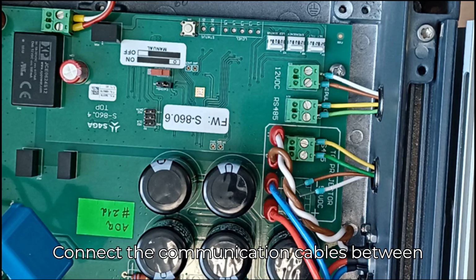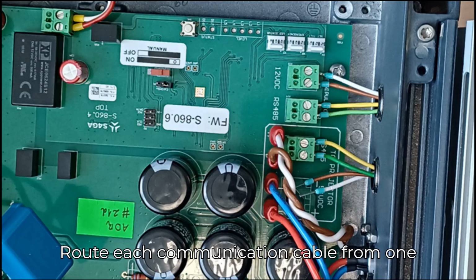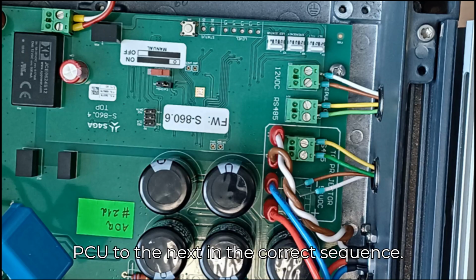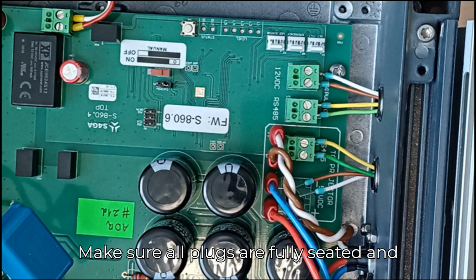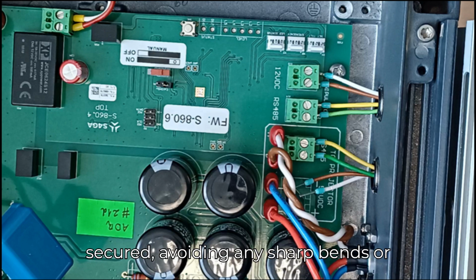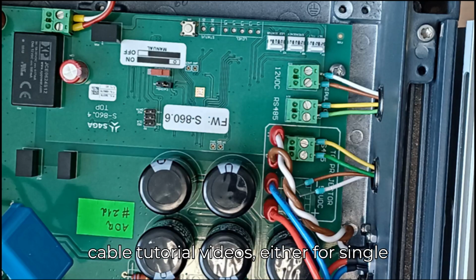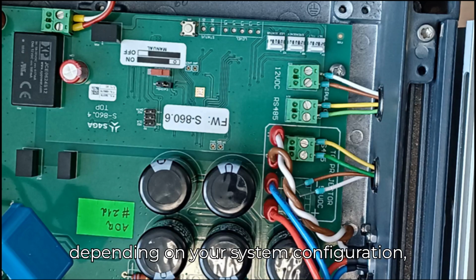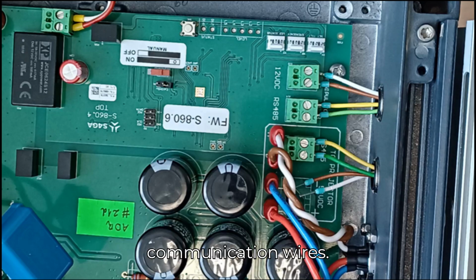Connect the communication cables between PCUs. Route each communication cable from one PCU to the next in the correct sequence. Make sure all plugs are fully seated and secured, avoiding any sharp bends or cable strain. Refer to the dedicated communication cable tutorial videos, either for single cable PCU or dual cable PCU, depending on your system configuration, to learn how to correctly connect the communication wires.